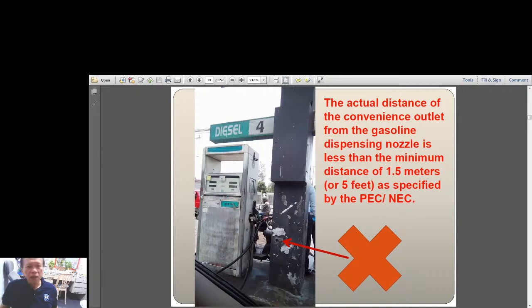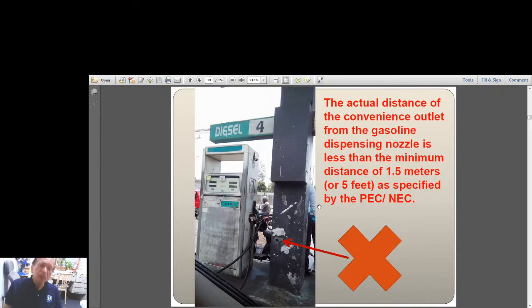Okay, and it is a double whammy because this is another picture showing it. If the panel board is here above, you would see an outlet here below, and therefore it is even closer to the gas dispenser. No? Okay, so it's a violation of the code, really. The engineer who signed the plans does not know his code. The one to supervise the project also doesn't know the code, and much more the building official, the inspector who allowed this to be done. So anyway, let's make it a lesson. It should not happen. It should not be done again in other parts of the country.